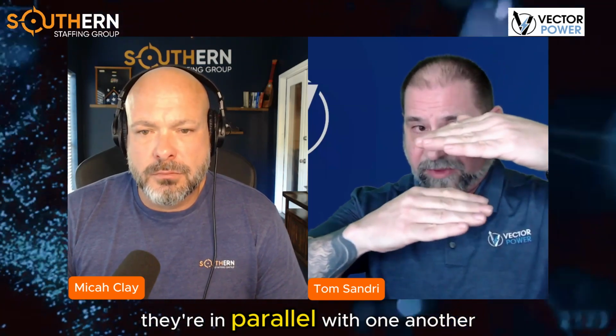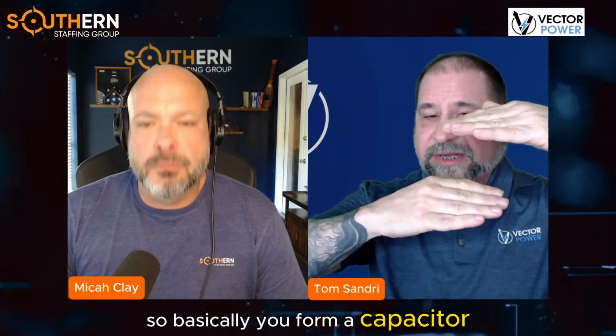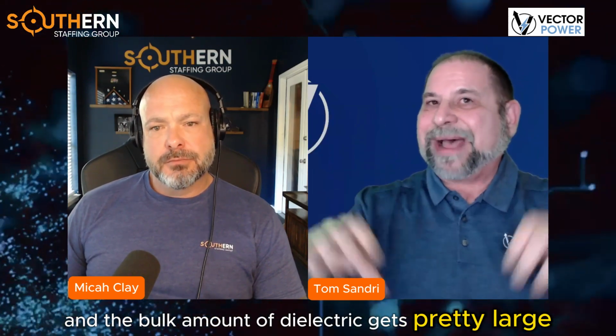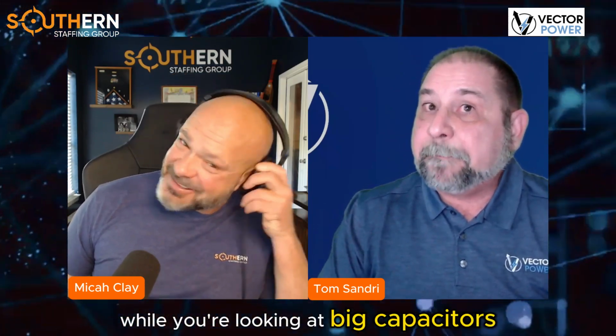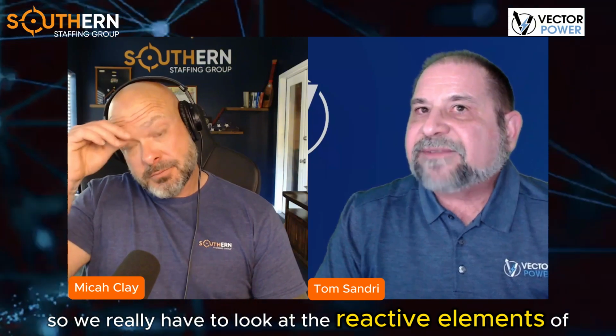Now, why does this come into play? When you think of a cable, you've got a conductor and a metallic shield, in parallel with one another. In the middle is the dielectric. So basically, you've formed a capacitor. Now, when you look at lengths of cable, the surface area of those two plates and the bulk amount of dielectric gets pretty large. When you're looking at 1,000, 2,000 feet, or 7 miles or whatever of cable runs, you're looking at big capacitors. So we really have to look at the reactive element, capacitive reactance, and what effect this is going to have on your power supply.